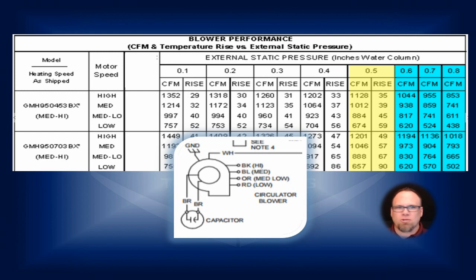So the older ductwork that's in the homes oftentimes is not sized correctly for the modern equipment. It was sized to move less airflow. So we're already starting off with our hands tied on the ductwork, because usually it's all in finished ceilings and walls and floors and things like that. So we have to do what we can to make the airflow right in the home. And what we can do is, one, make sure that the filter is sized properly, and also make sure that it's not restrictive. The fiberglass filters, although nobody likes to use them because, well, you can hold it up like this and see right straight through it, and it's not going to catch much except for the big stuff.